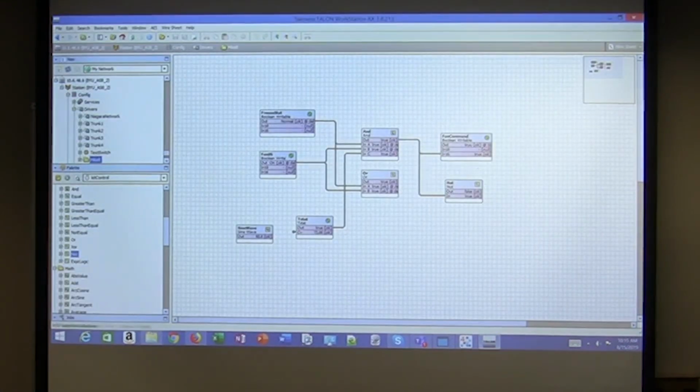So these objects or Boolean points don't count against our point count, but when you tunnel into a device and go into its points folder, anything you bring in under the points folder that's from the device itself is counted as points against you.